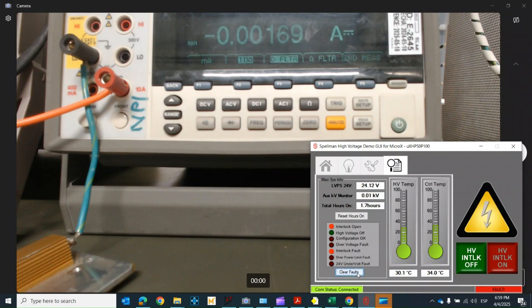It must be noted that even after clearing the fault, if the interlock is not placed back at the 15-pin connector, it will not allow to enable the high voltage on signal.